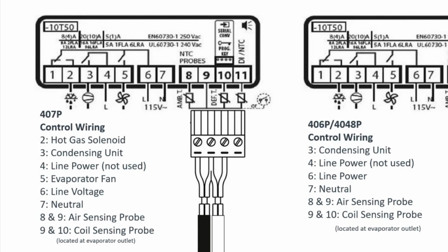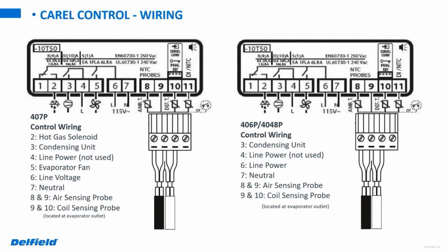You have your condensing unit, line power, everything coming in, your evaporator fan. So the fans on these, basically when the unit's in a cooling mode, the fan will run. Otherwise, the fan is off. And then you'll notice the probes on that. So the probes on these, in a lot of our different models, you'll have separate probes for the evaporator coil and for the air sensor. On this one here, if one of them fails, you're actually going to be replacing both. They come together as a harness, plugs into the back of the control, and then you'll just run the probes to the appropriate location, whether it's on the suction line or in the return air on that.